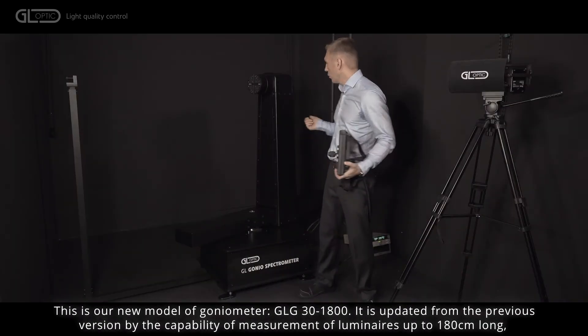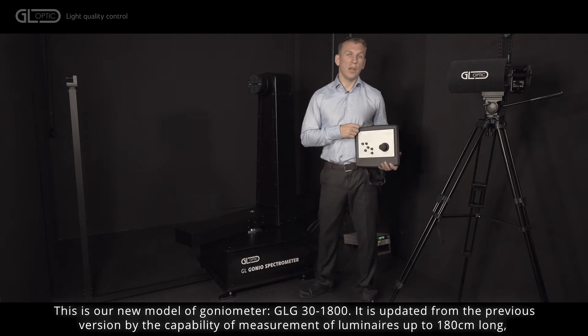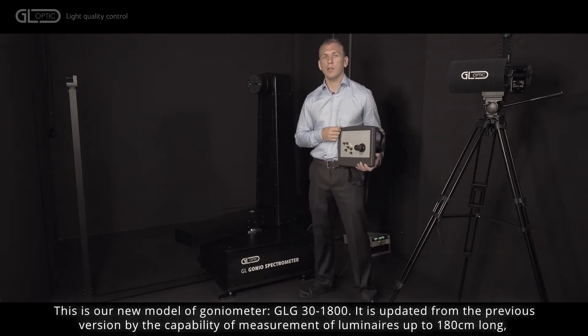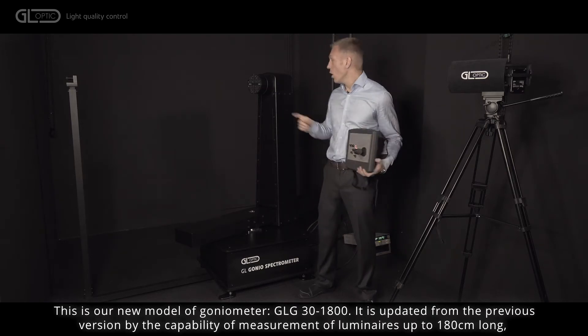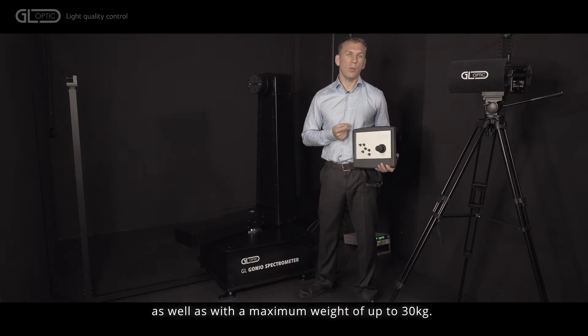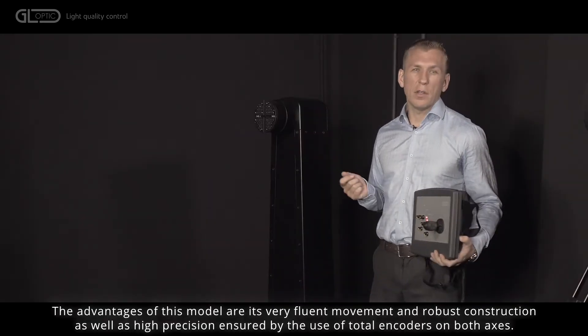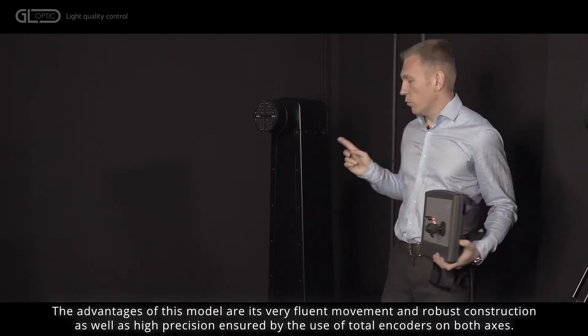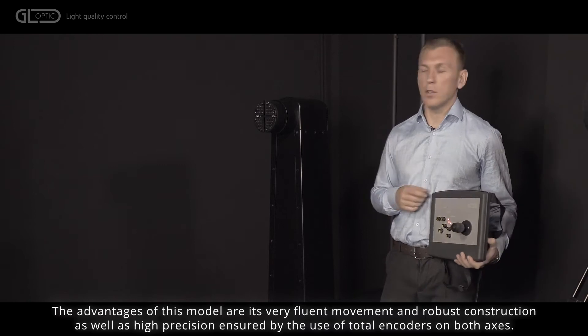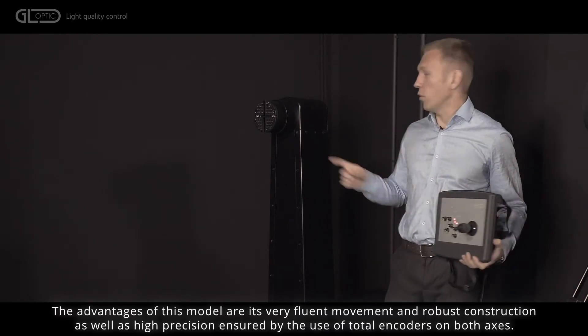This is our new model of goniometer GLG 30-1800. It is updated from the previous version by the capability of measurement of luminaires up to 180 centimeters long as well as with a maximum weight of up to 30 kilograms. The advantages of this model are its very fluent movement and robust construction, as well as high precision ensured by the use of optical encoders on both axes.